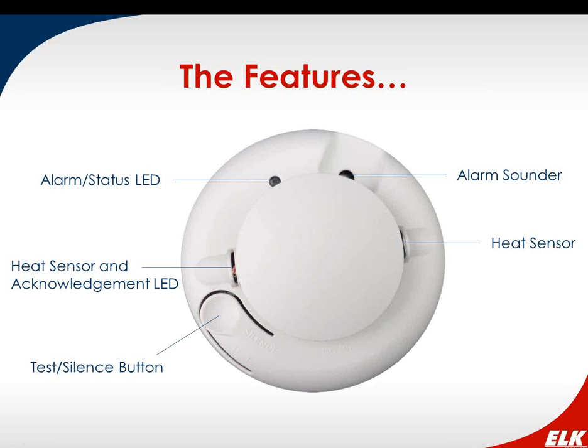Now that sounder with one smoke detector is 85 decibels at 10 feet, and it is in the standard temporal pattern that you need for fire, so it's going to be sounding in that 3-tone, 3-cadence pattern when it goes off.